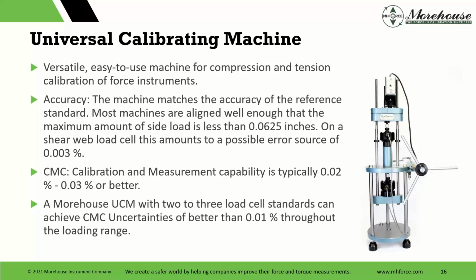So then we get to the title of this webinar, the Universal Calibrating Machine. It's a versatile, easy to use machine for compression and tension calibration of force instruments. The machine matches the accuracy of the reference standard. There is some additional uncertainty that needs to be accounted for. Most machines are aligned well enough that the maximum amount of side load, per load cell spec sheets, is about 30 parts per million. Typically, I tell customers and help them with uncertainties, they're getting better than 0.02 to 0.03%. Some will go to 0.04, and it depends.